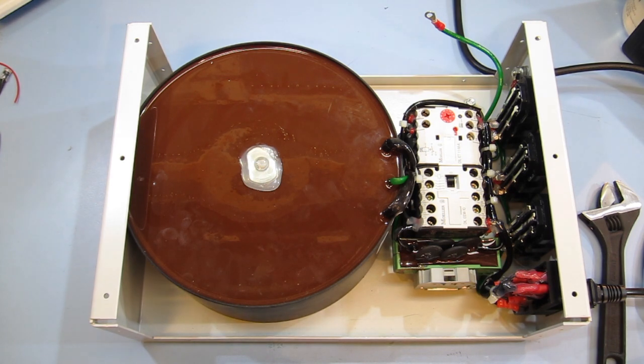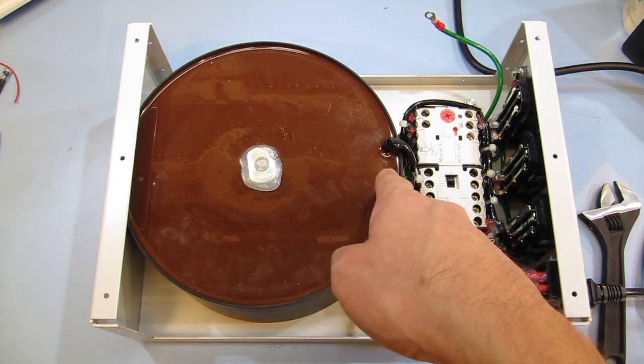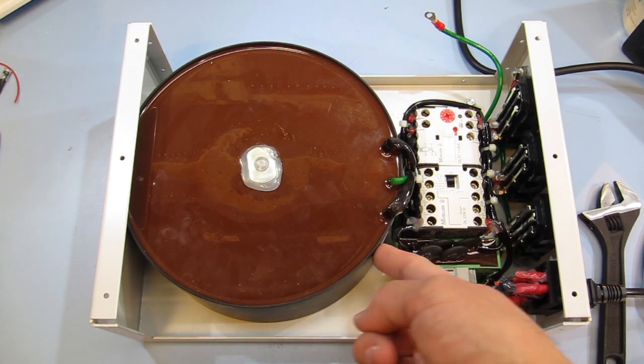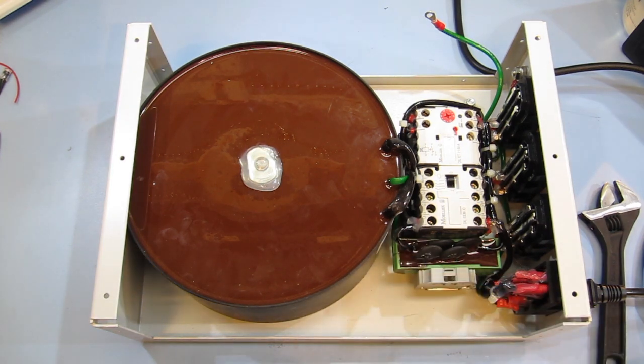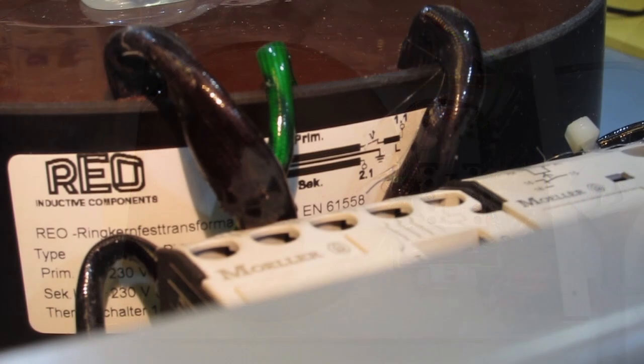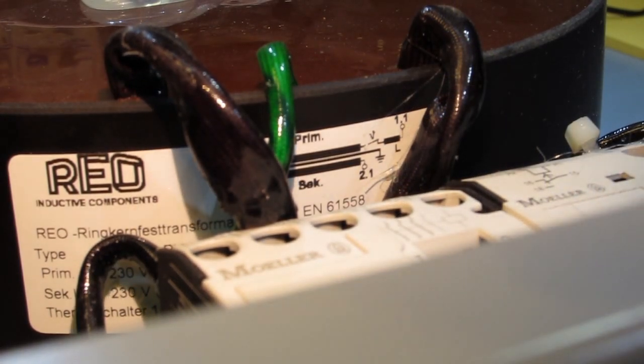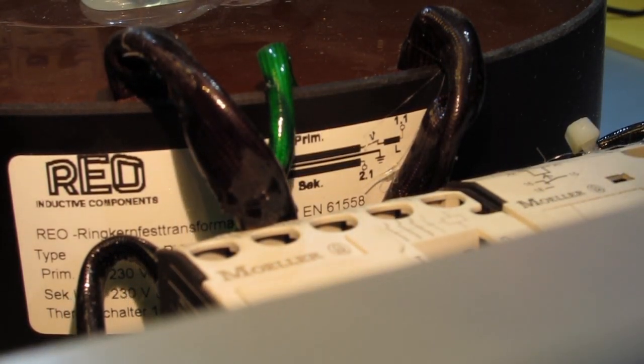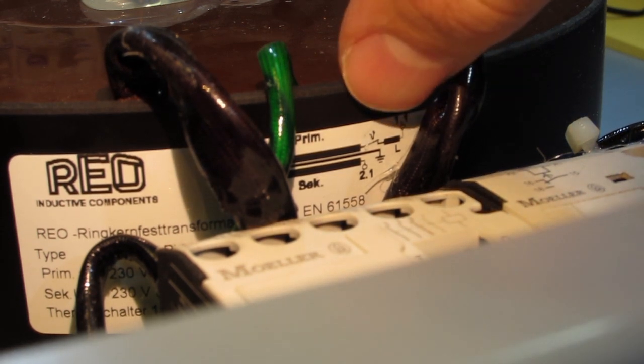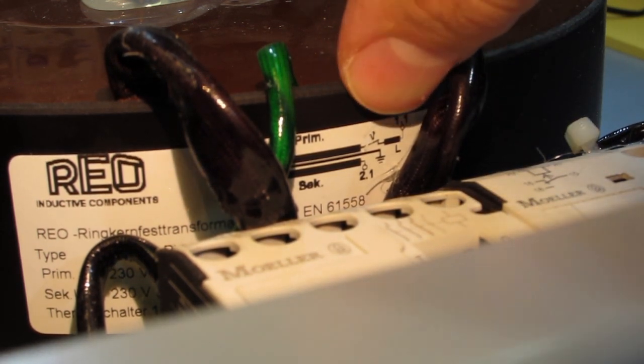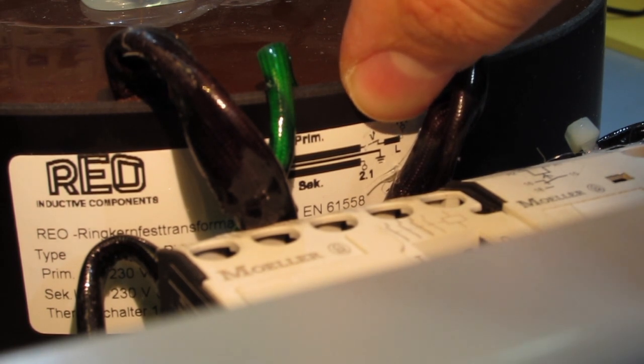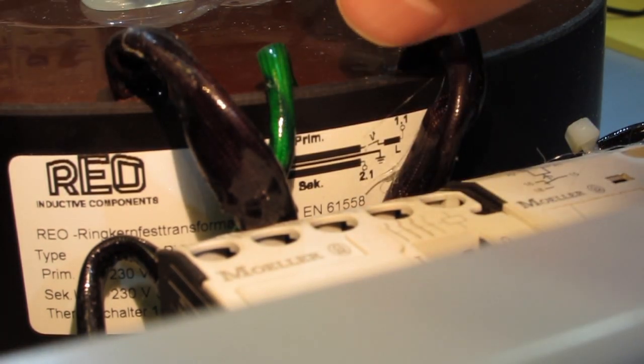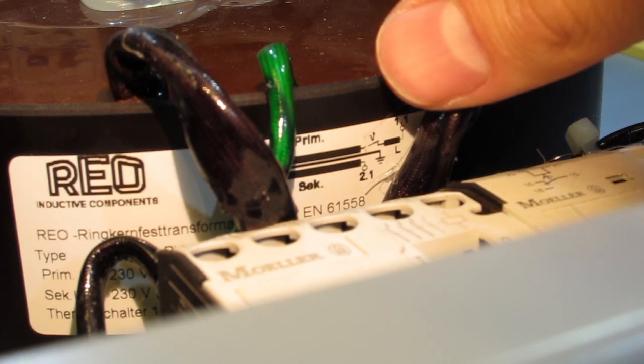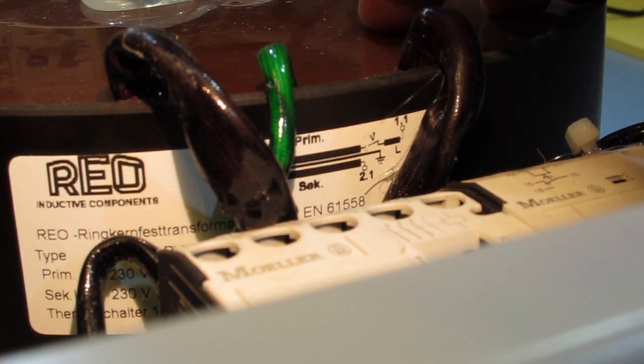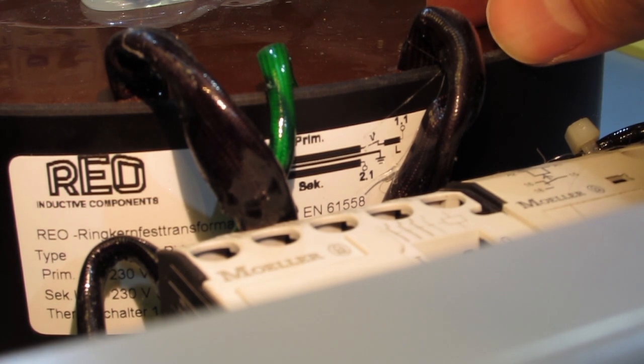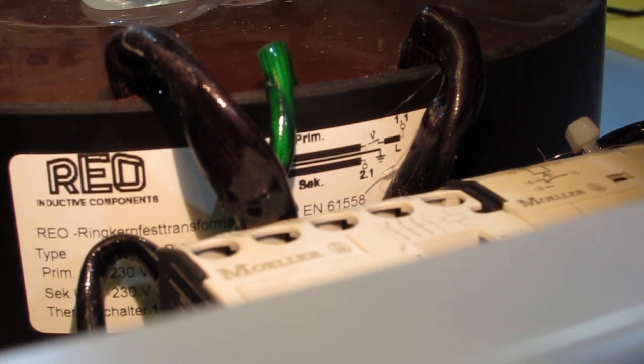So next we'll have a quick look at what this earth wire is doing, and then we'll see how we can fit the 13 amp socket into the top lid. Okay, so that's about as good as I can get on the label here. So we can see there's a primary with a thermal fuse, which on the label I think it says 100 degrees, so if the temperature of the transformer exceeds 100 degrees centigrade, then the transformer is probably ruined because there's no way you'll be able to replace that thermal fuse.